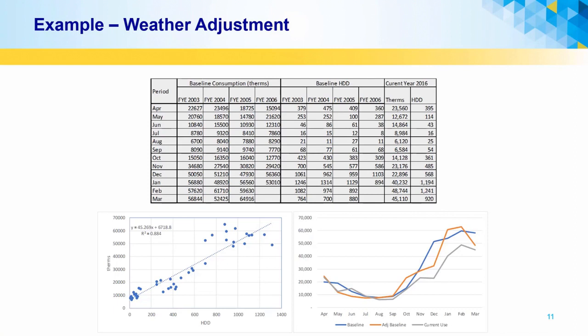Least squares adjustments can be done to the baseline or to the current year's data. The baseline usage can be moved forward using current year's weather to compare to the current actual usage, or the current actual usage can be adjusted for comparison to the unadjusted baseline. The more common method is to adjust the baselines for weather, since more months of data are available.